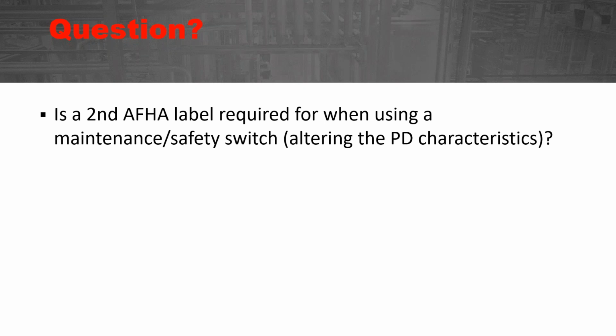Is a second AFHA label required when using a maintenance or safety switch, altering the protective device characteristics? I think this is more for you, Jay. Yeah, so the AFHA is the arc flash hazard label. So the question is, if we put our equipment into a maintenance mode or a safety switch mode, which alters the protective device characteristics, such as it reduces the instantaneous pickup from times 10 to, say, times 4, does that require an additional label? The short answer, I would say, is if it reduces the incident energy, the answer is no. If it increases the incident energy for some reason, I would say you would probably want that highest incident energy label to be there on the panel.